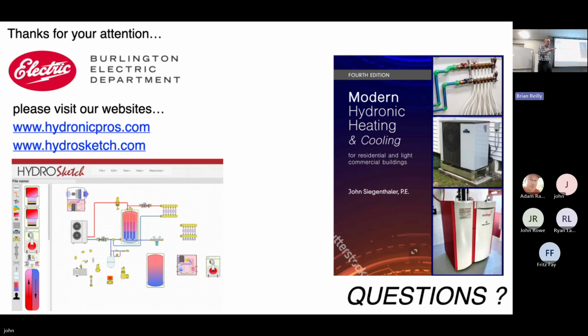this is exactly how you wire it. You have all these terminal boards with all these terminals. This is where that sensor goes. Sensor C1 goes to terminal C1 on the heat pump. Is the heat pump itself doing all of the control work? It depends. Many of the modern heat pumps can, for example, call the boiler automatically if they need to. Can they operate zone valves? Usually not. Usually you're going to need another Taco box that will do the zoning for you, and then it signals the heat pump to turn on. And again, you've got several companies that can provide that zoning box.